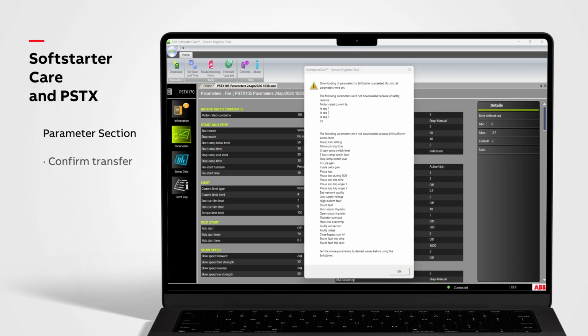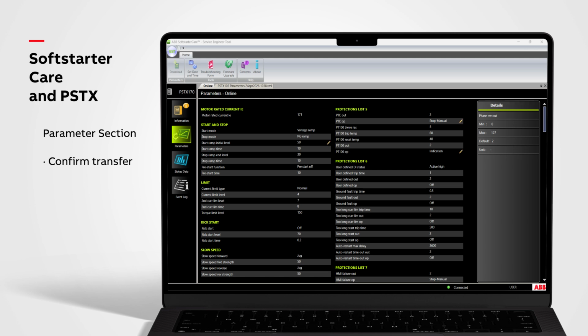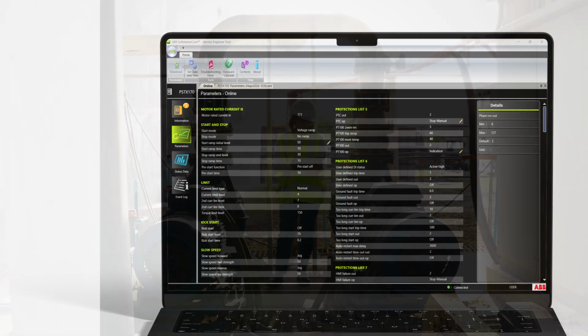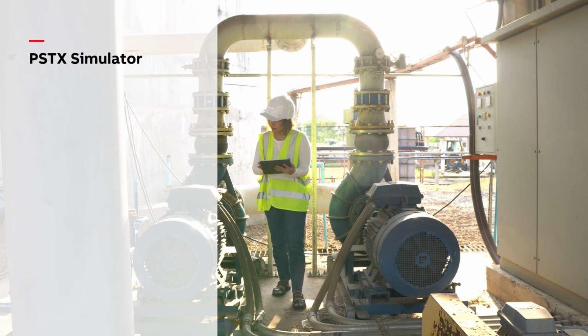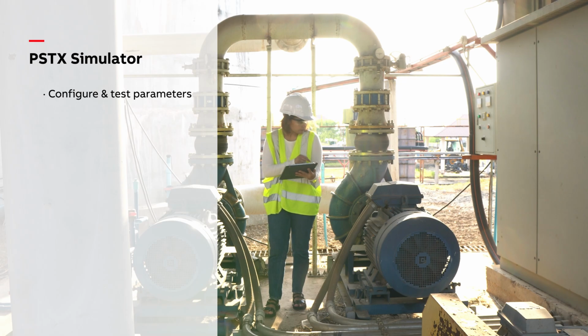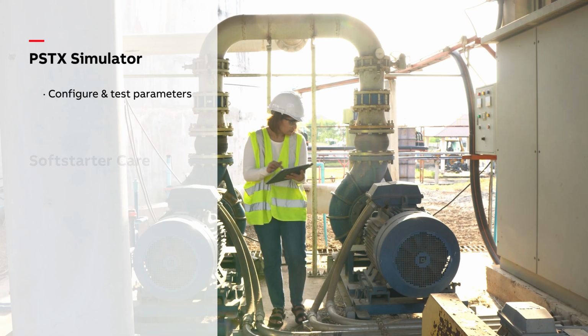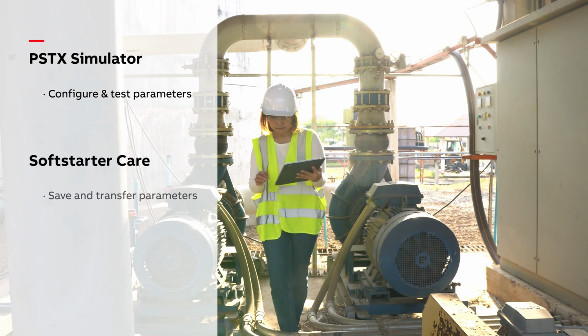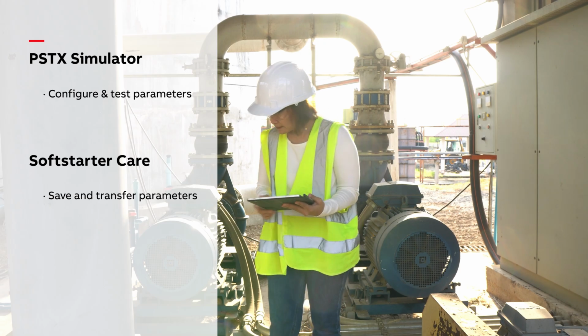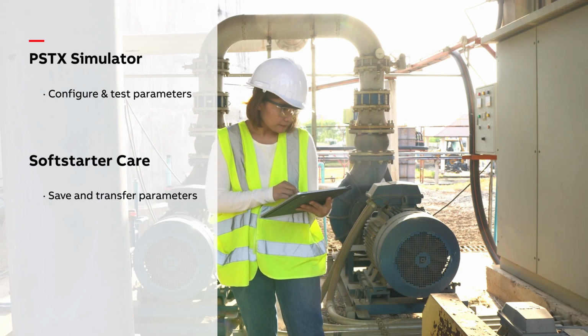After the download, a pop-up window will indicate any parameters that cannot be transferred, such as the Softstarter ID and nominal current values. Click OK to confirm. The parameter transfer is now complete. The PSTX Simulator allows you to configure and test parameters directly from your laptop. Softstarter Care, on the other hand, lets you save and transfer parameters to multiple Softstarters in a fast and simple way.